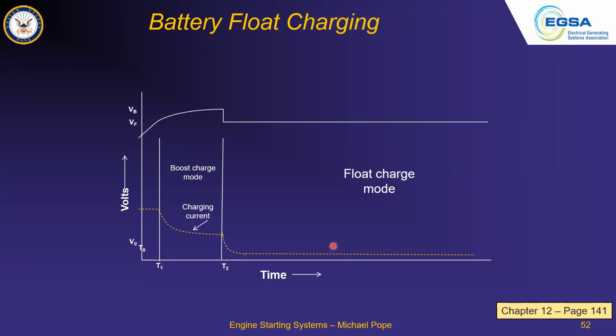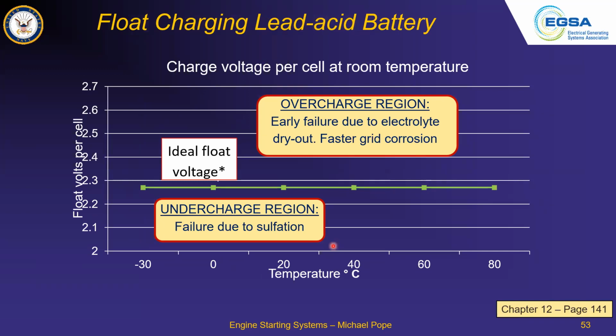It turns out that the voltage set on the battery charger is really critical. This is a number that can be obtained from the battery manufacturer - what rate should we be charging that battery. In this case here, we've taken the example of 2.28 volts per cell. So you multiply that by the amount of cells you've got, and that is the rate at which you should be float charging that battery. You don't want to go higher or lower than that, because you'll either get faster grid corrosion, or you'll get failure of the battery due to sulfation, and you'll get lower performance as well. So this is going to shorten the life, and this is going to shorten the performance.